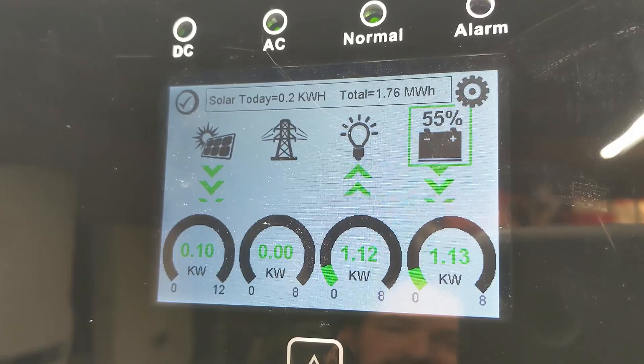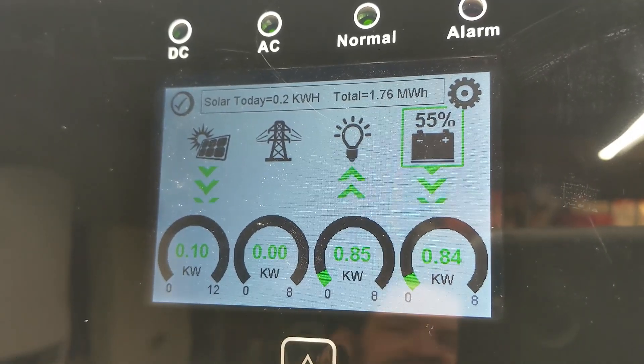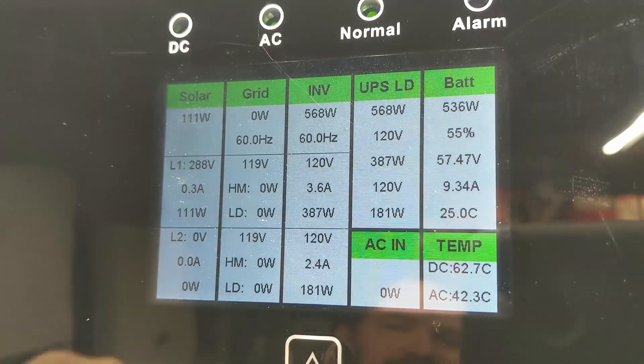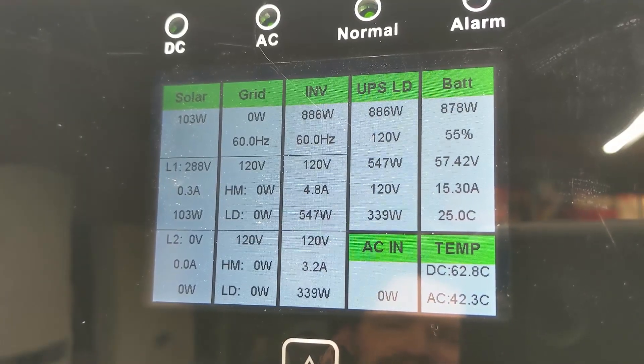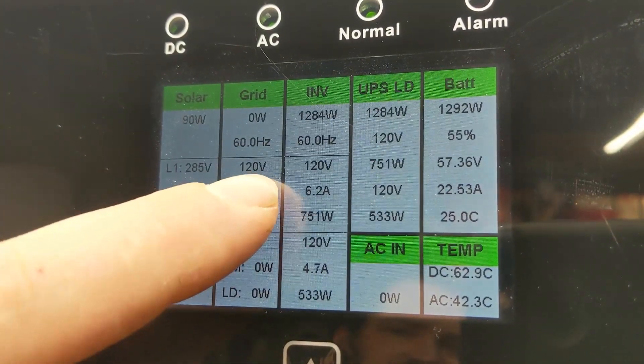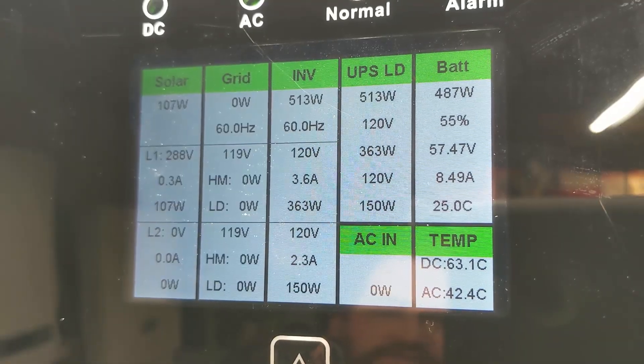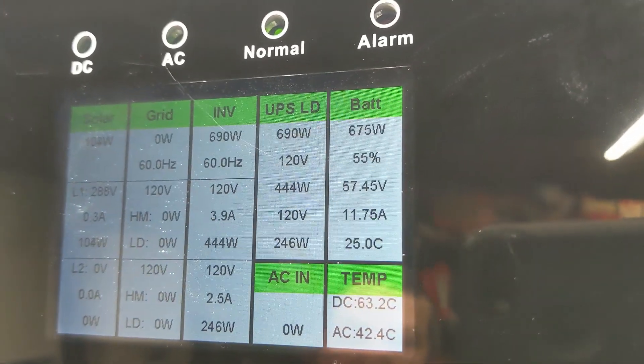On the left we have the solar power in, next we have grid in which is zero, then power out to the loads, and power from the battery — it details everything. We have only about 100 watts coming in on L leg one, and it shows the voltage, amperage, and wattage. Grid power still shows voltage on the screen but there's not actually voltage on there. The inverter column shows 800 watts total at 60 Hz — line one is 6.3 amps, line two is 4.7 amps. Then there's the total in from the battery. I haven't hooked up the temp sensor yet so that just says 25°C. It also gives the internal inverter temperatures. The AC IN down here is for the generator port, which I'm not using right now.